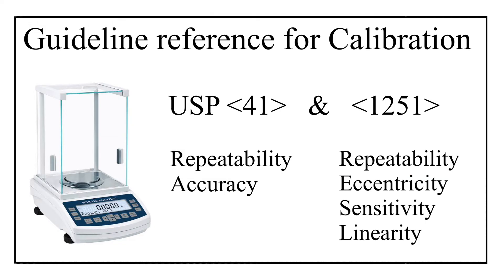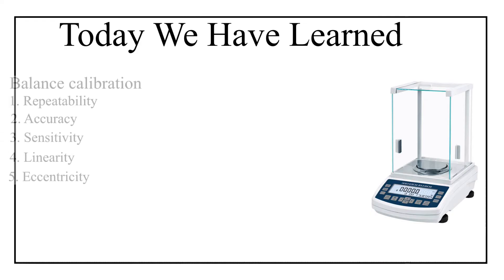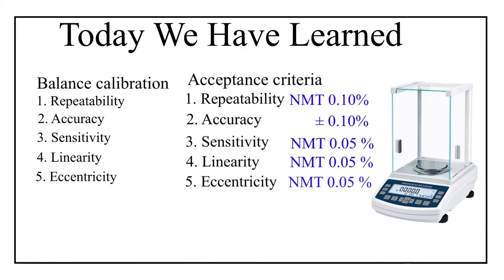Let's quickly rewind today's learnings. We learned three things about balance calibration. First, there are five calibration parameters: repeatability, accuracy, sensitivity, linearity, and eccentricity. Second, repeatability and accuracy share the same acceptance criteria of not more than 0.10%, whereas sensitivity, linearity, and eccentricity share an acceptance criteria of not more than 0.05%.